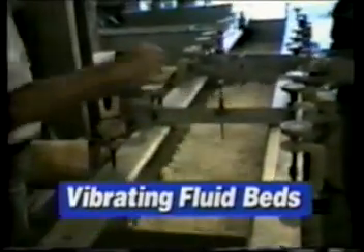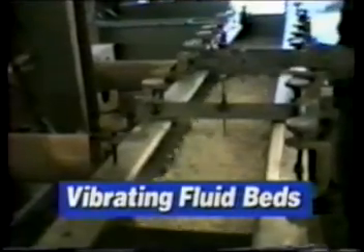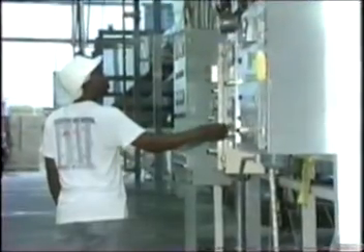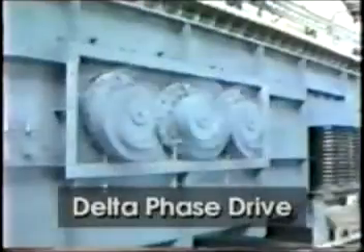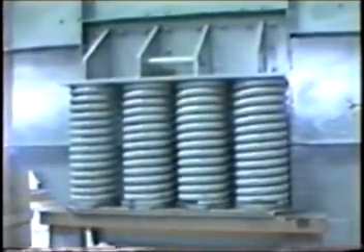Fluid beds are extremely versatile. However, not all materials can be easily fluidized. Materials with a wide particle size distribution or a bed of large particles may be better suited for a vibrating fluid bed, where the product is transported and fluidized by a combination of air with vibration assistance. For optimum ease of process control, Carrier's completely electronic delta phase drive allows vibration angle and retention time to be automatically and instantaneously changed while the machine operates, allowing for changes of product type and characteristics.